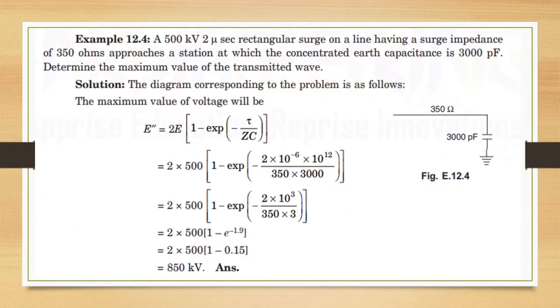Numerical: A 500 kV, 2-microsecond rectangular surge on a line having a surge impedance of 350 ohms approaches a station at which the concentrated earth capacitance is 3000 pF. Determine the maximum value of the transmitted wave. Maximum voltage: e″ = 2e × (1 − e^(−τ/ZC)) = 2×500×(1−e^(−1.9)) = 2×500×(1−0.15) = 850 kV approximately.